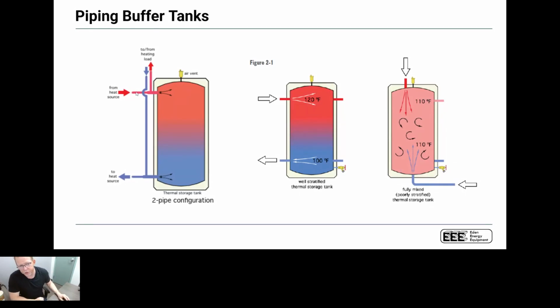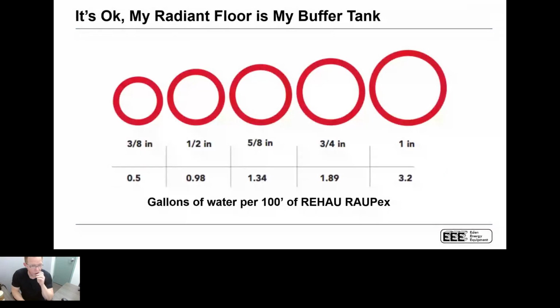This particular setup I'm a big fan of. It's a two-pipe configuration. With a two-pipe configuration, what you do is the piping where you feed into the unit, as you get right close to the tank, you're going to upsize that piping. And what ends up happening is it ends up being a point where the velocity of flow drops down. So you can actually be heating the space and charging the buffer tank at the same time. And whatever temperature is leaving your air-to-water heat pump is actually going direct to load as well. So it's a really, really slick way to do the configuration.